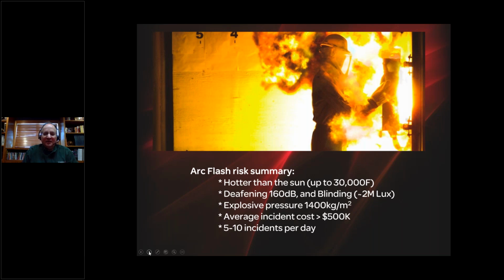The fact that at three times hotter than the surface of the sun, up to 30,000 degrees Fahrenheit, copper or steel are vaporized, turned into a plasma gas, and propelled at up to 200 miles an hour. It's deafening. The high lux intensity is sufficient to score the cornea of a human eye. And the explosive pressure, once the arc flash incident energy exceeds 40 calories per centimeter squared within the arc flash hazard boundary, is sufficient to collapse eardrums and collapse lungs. The average cost is more than $500,000, but I have been involved as an expert witness in suits that are tens of millions of dollars.